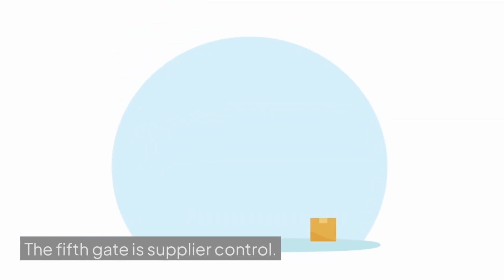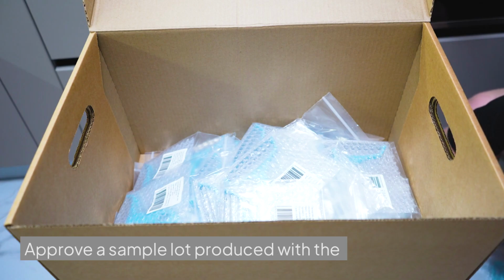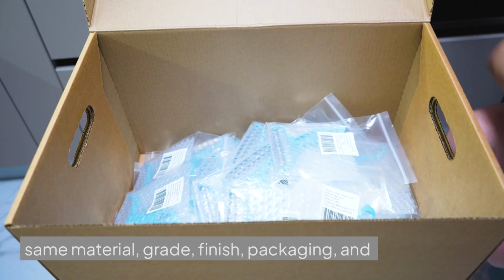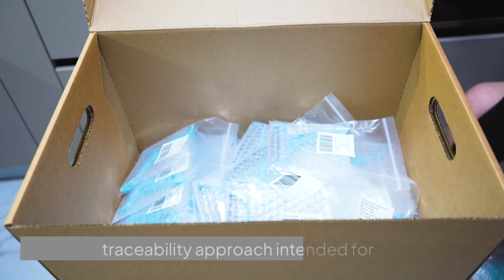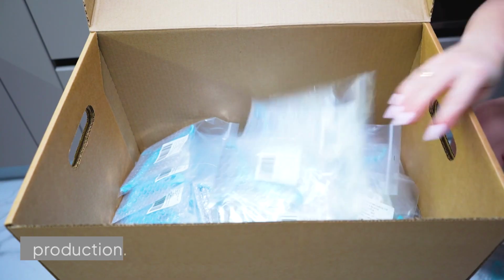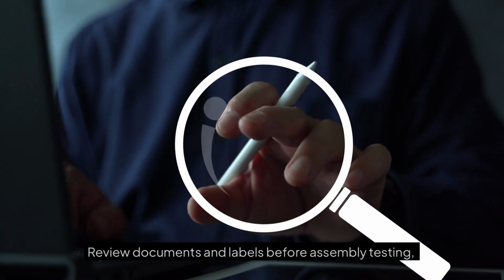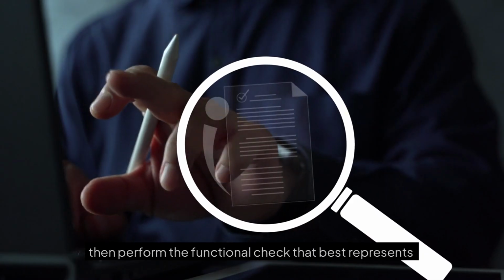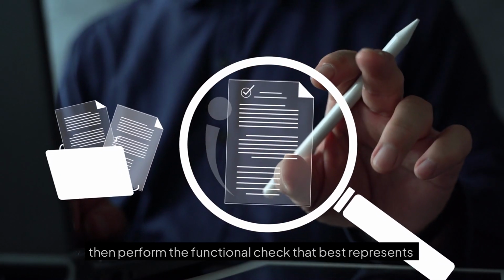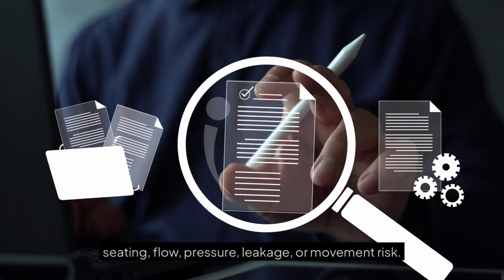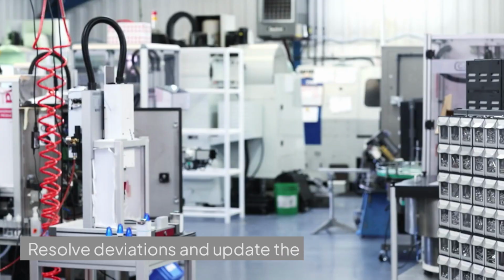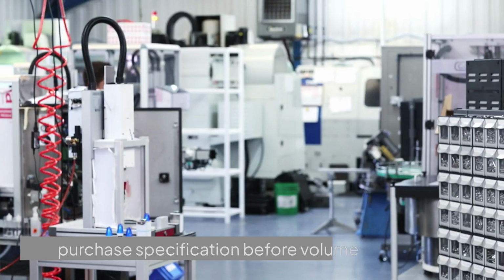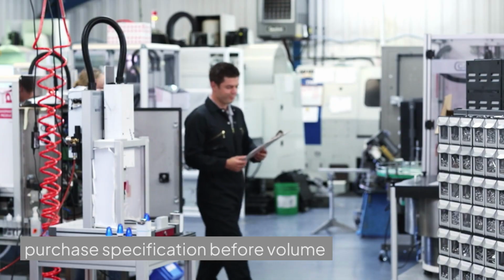The fifth gate is supplier control. Approve a sample lot produced with the same material, grade, finish, packaging, and traceability approach intended for production. Review documents and labels before assembly testing. Then perform the functional check that best represents seating, flow, pressure, leakage, or movement risk. Resolve deviations and update the purchase specification before volume release.